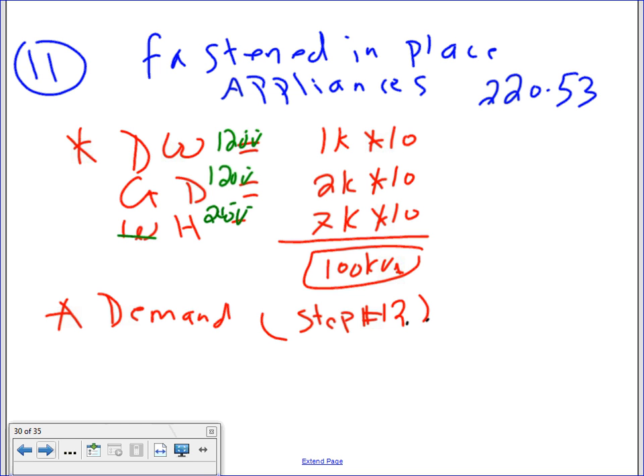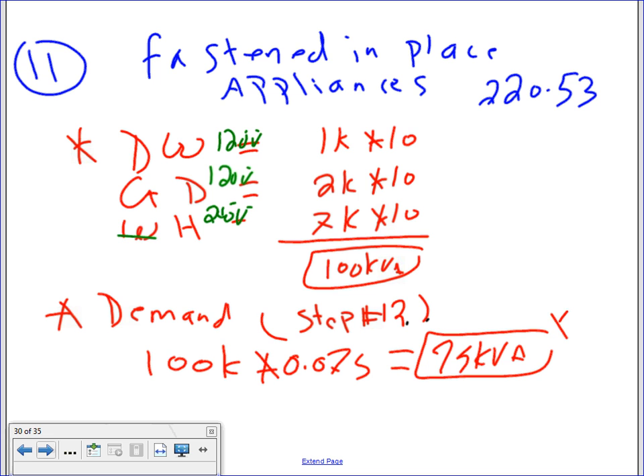That will be your demand. The code says, guys, if you have 4 or more fastened in place, you have to cut it by what? Anybody remember that number? 0.75. So then you're going to take the 100K, multiply it by 0.75. That's coming from 220.53. And that will get you a healthy 75 kVA. And that's the number that you're going to use. Do me a favor. Keep room here because I'm going to do the neutral here.